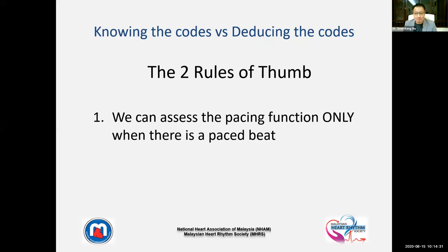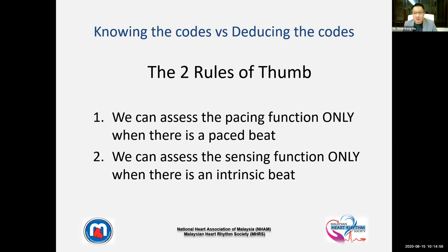Rule number one is, if you are faced with an ECG of a patient implanted with a pacemaker, you can assess the pacing function of the pacemaker only when there is a pace beat, and this is a fact. You will not be able to tell the pacemaker function without any pace beat. In the same concept, in the same vein, we can assess the sensing function of that pacemaker only when we see an intrinsic beat. If you see the pacemaker with all pace beats, we are unable to assess the sensing function. That's the basic fact you need to take away.